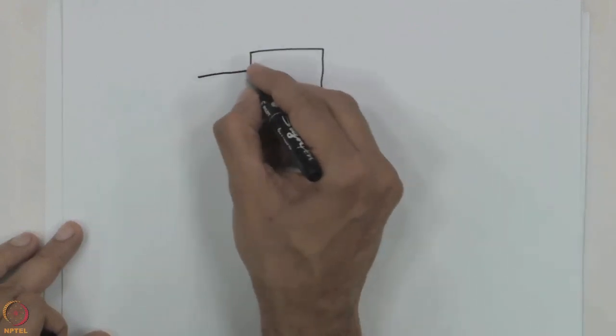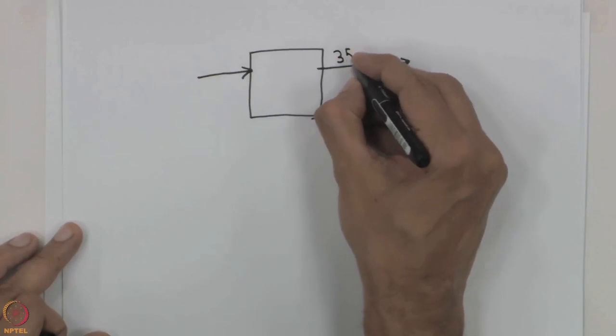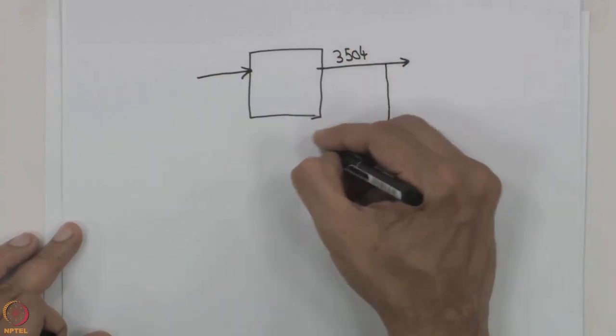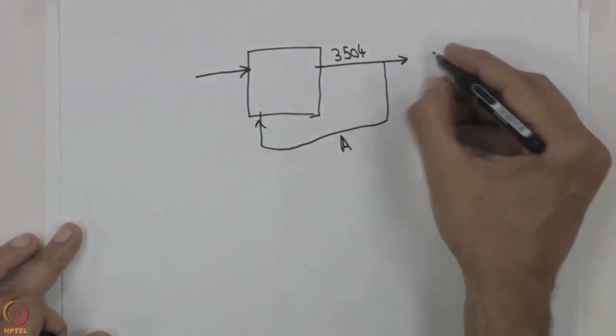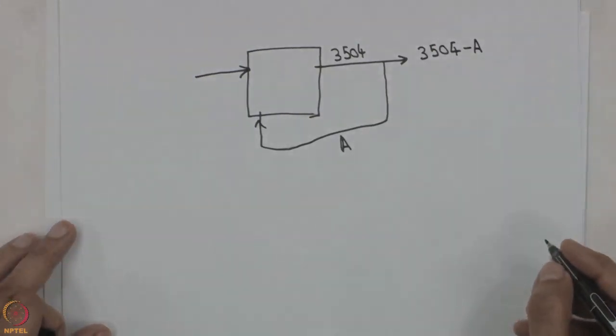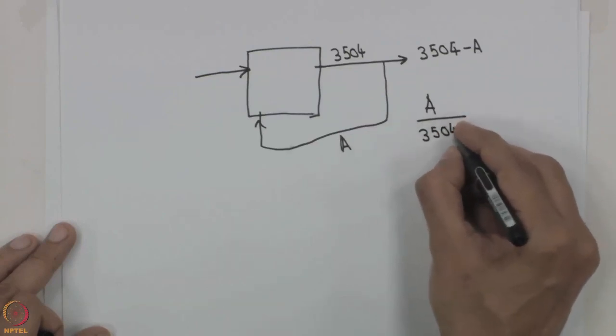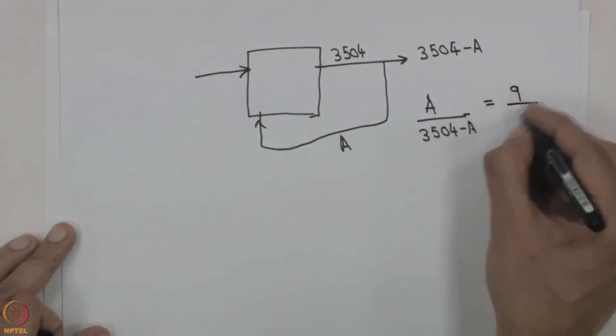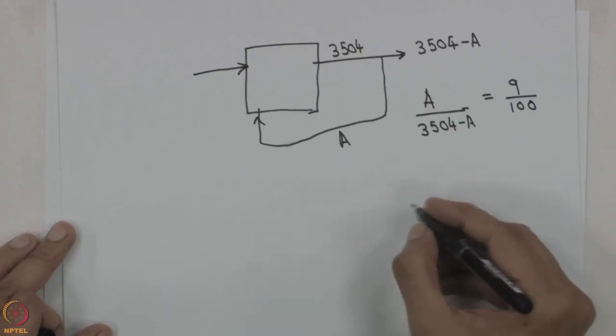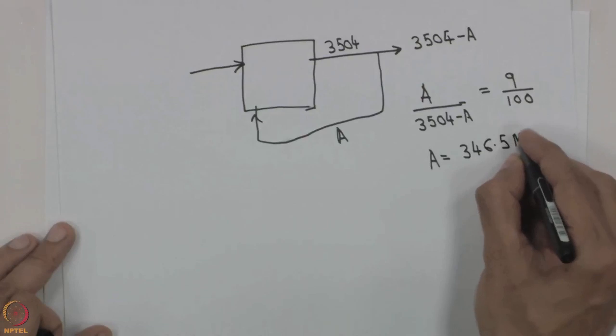This was the gross generation. Now considering auxiliary consumption: the gross generation is 3504 MUs, out of which we have auxiliary consumption A being used internally, and the net output is 3504 minus A. We are told 9 percent is the auxiliary consumption, meaning A divided by the net output (3504 minus A) equals 9 divided by 100. Solving this, A turns out to be 346.5 MUs.